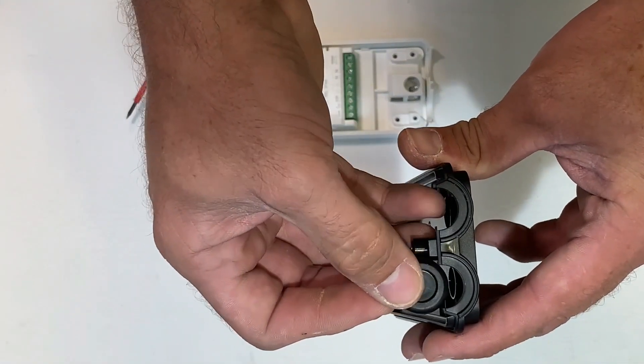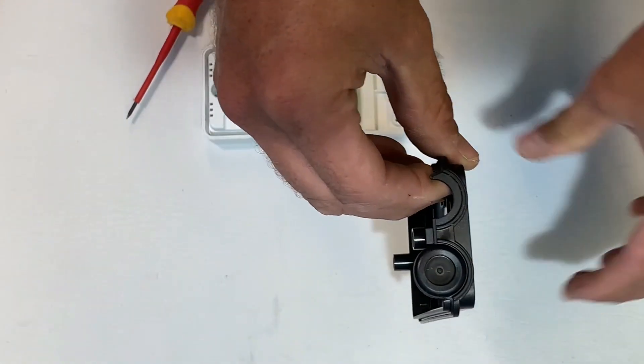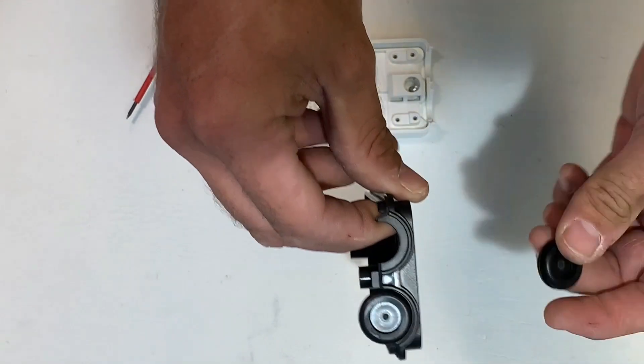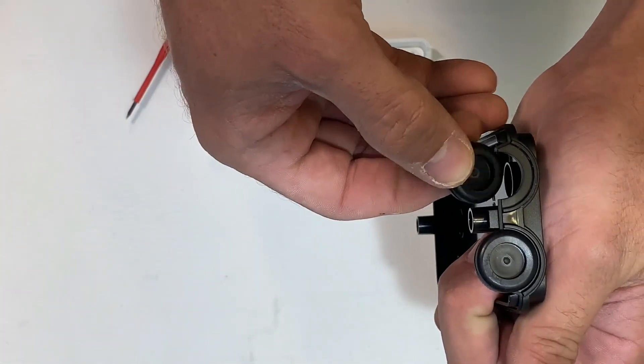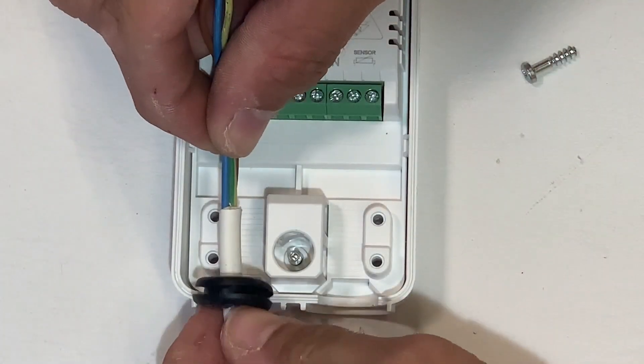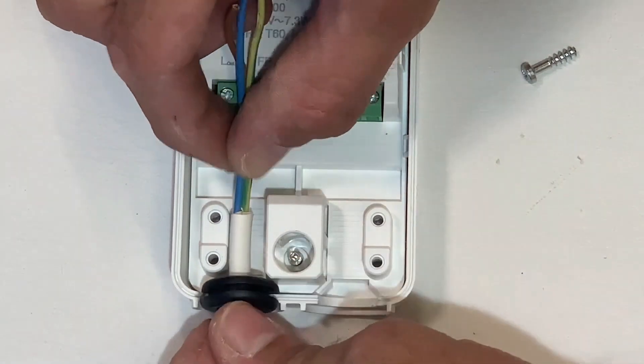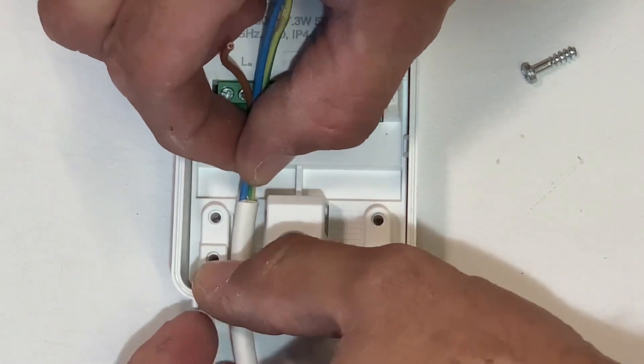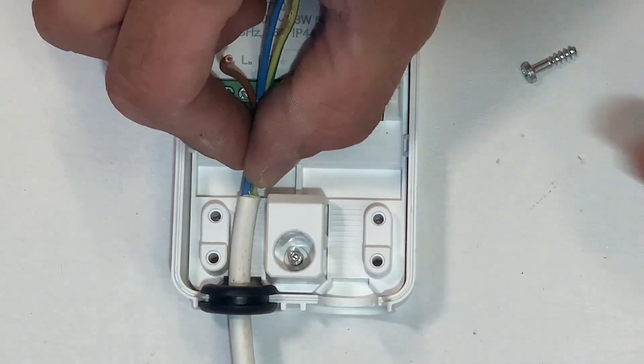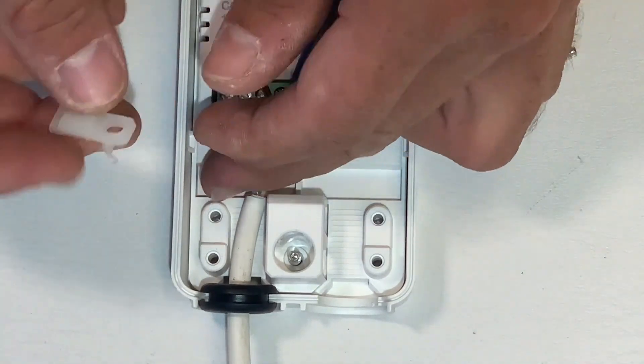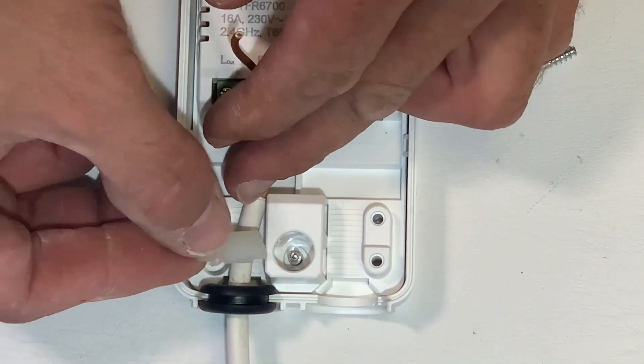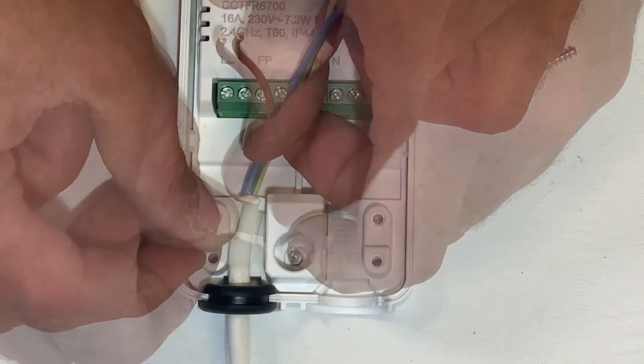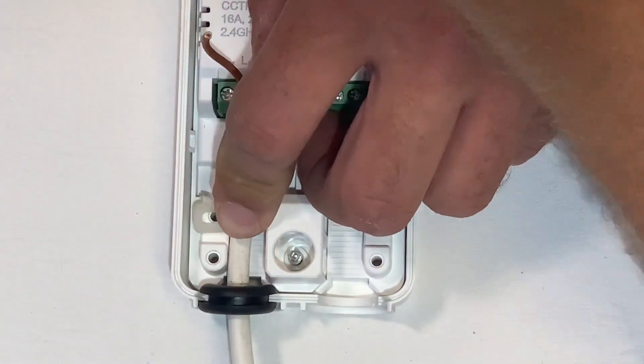To maintain the IP rating of the product, there are two grommets that the cables will pass through which fit into recesses in both the top and bottom casings. Both cable entries have clamping arrangements for different sized cables. By having two positions, the clamp can be fitted in the appropriate location to suit the size of cable you're using.